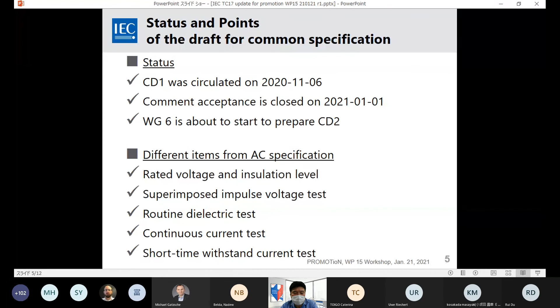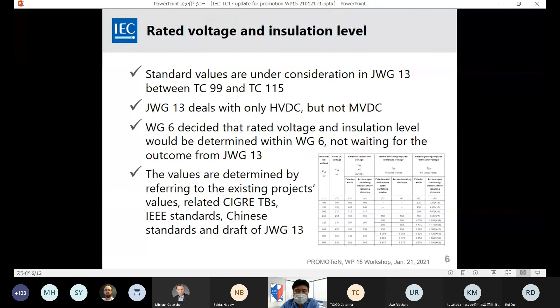Concerning rated voltage and insulation level, standard values are now under consideration in joint working group 13 between TC99 and TC115. Joint working group 13 deals with only HVDC but not MVDC. And so working group 6 decided that the rated voltage and the insulation level will be determined within working group 6, not waiting for the outcome from joint working group 13. The values are determined by referring to the existing project values, related CIGRE technical brochures, IEEE standards, Chinese standards, and the draft of the joint working group 13.